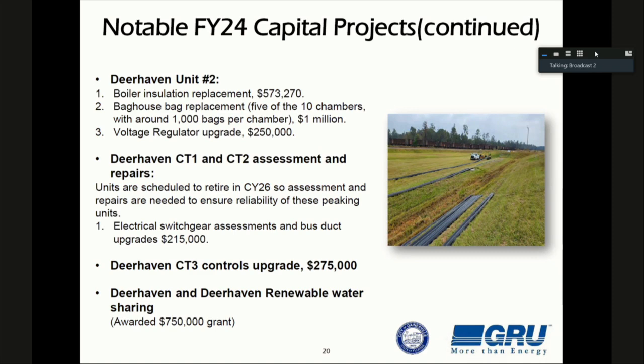For all of our solid fuel plants, i.e. Deerhaven 2, which burns coal, and the biomass plant that burns wood, we have baghouses because in the actual emissions we have particulate matter that has to be removed from our emission system. We don't discharge particulate matter to the atmosphere - we capture it in bags, and then we dispose of that properly. Those baghouses are pretty extensive. In Deerhaven, there are 10 compartments.